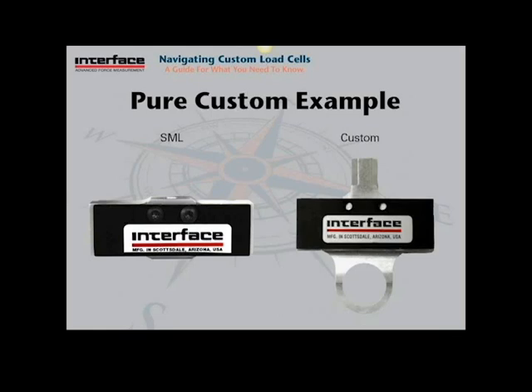On the bottom, they had us put together a place so they could insert bearings and give a rod-end effect so that the load, even if it was, let's say, off axis, could be directed through the axis of the load cell. Besides, of course, the redesign of the fixture, the testing fixtures in-house also had to be modified, so that's what contributes to the increased NRE charges.